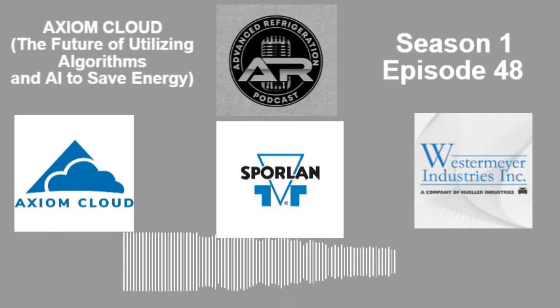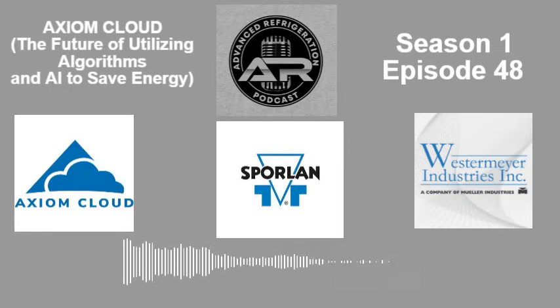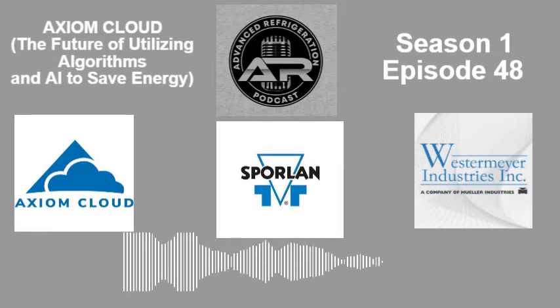Always. Well, how many stores have you dealt with that have been under remodel, where they change out the cases, they change out the refrigerant, but they never change out the sizes of the liquid headers? Then basically you get this mix where the head pressure is either the same or even sometimes lower, because technicians sometimes mess up where they've set everything for suction dew point their whole life. Now with these large glided refrigerants of 12 to 10 degrees, if you set something to a 40 degree saturated dew point, you're probably getting 30 degrees on your liquid side, or your bubble point.